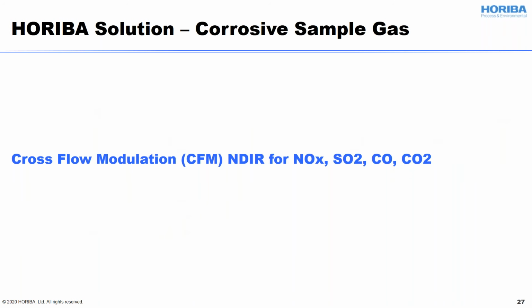The other issue is that the sample gas is highly corrosive, since an incinerator application likely contains gases such as HCl, HF, SO3, etc. Those are highly corrosive, and they will rust or damage the parts in the sample gas sample system or the analyzer itself. From this section, I will talk about technology, how the analyzer can be durable, and the other one is the sample system, how we can get rid of those unwanted components. First of all, I'm going to talk about the HORIBA patented cross-flow modulation technology.